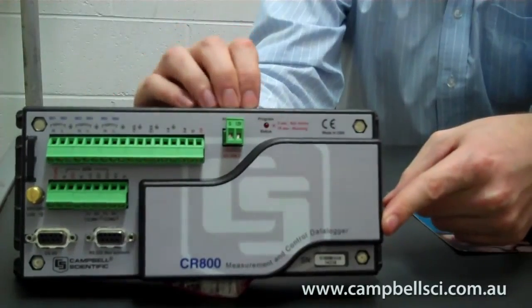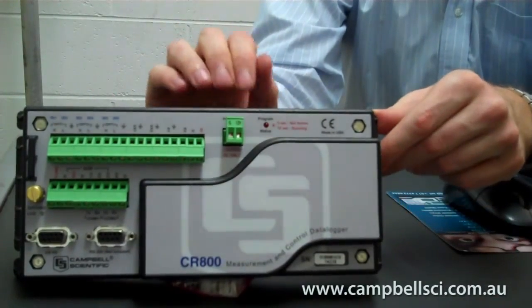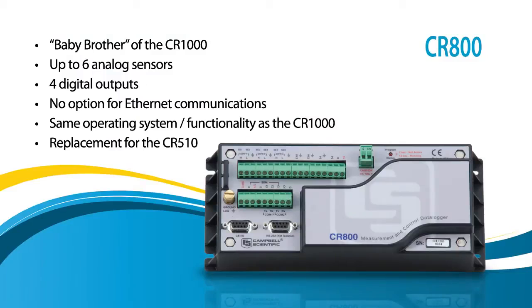The CR-800 is also missing a peripheral port, so you can't connect an Ethernet cable to this one and you can't expand its memory with a compact flash card. Otherwise, the programming is the same — it uses the same programming language and all the same instructions are supported. It supports DNP3 and Modbus as well. For those of you used to the older loggers, this has replaced the CR-510.